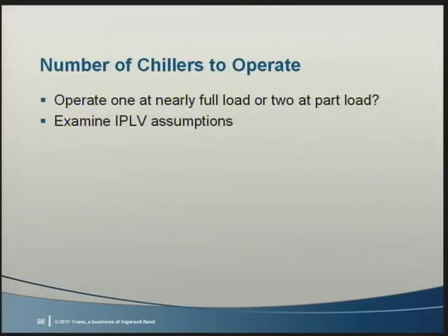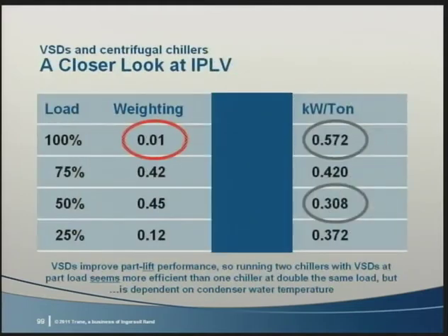Many in the industry receive chiller performance from manufacturers who rate the chiller in accordance with AHRI 550/590. In the standard, a term, integrated part load value, is defined and data is provided to allow calculation of the IPLV. Looking closer and combining representative chiller performance values with the 4 chosen conditions for IPLV highlights another controversial industry issue. That is, the recent claims that running 2 chillers with variable speed drives at part load is more efficient than 1 chiller fulfilling the same load. Of course, if attention is focused on these numbers, the assertion seems authentic.